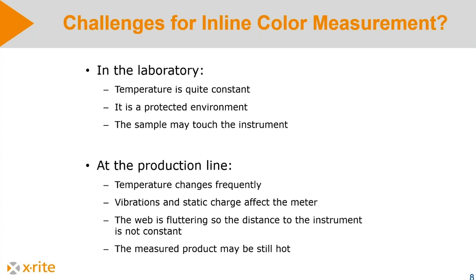Then we have, of course, vibrations, maybe even a static charge, which is influencing the measurement. The web is not touching the surface, of course, so we have a distance. If the web is fluttering, we need to have stable measurements even at a certain fluttering of the web. And of course, the measured product is still hot, and we have to compare it to the room temperature which you have in the laboratory. So this is the big difference why we have to make a special instrument for inline measurement.